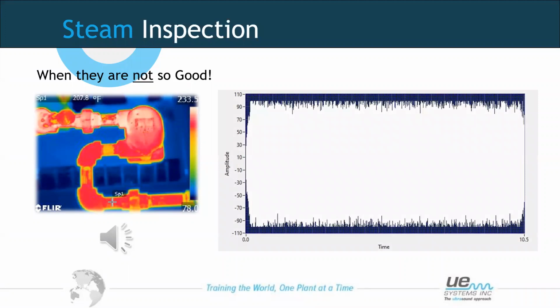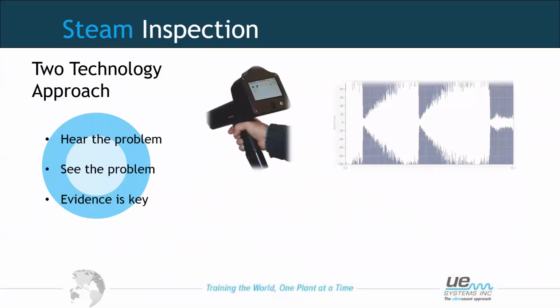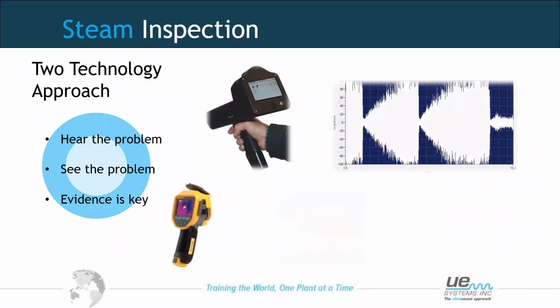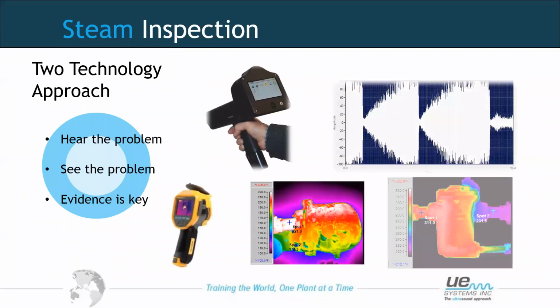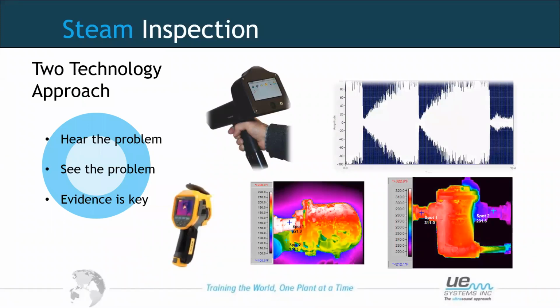Okay, and just as an example there, a thermal image showing a steam trap that is blowing through, that has high temperature on the outlet to the inlet. And that's what brings me on to talking about having a two technology approach, which sometimes can also help us with understanding the condition. Because one technology will be able to hear the problem, and the other technology will be able to see the problem. So for example, on a good steam trap, we would expect to see a higher temperature on the inlet of the trap and a lower temperature on the outlet because the condensate is going to be cooler than the steam on the other side.